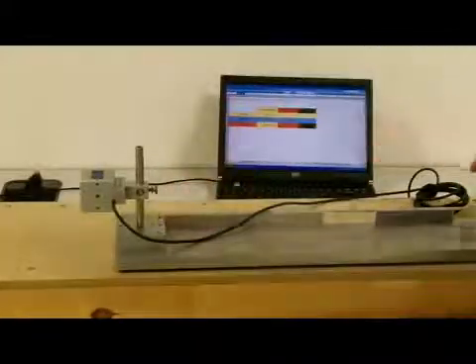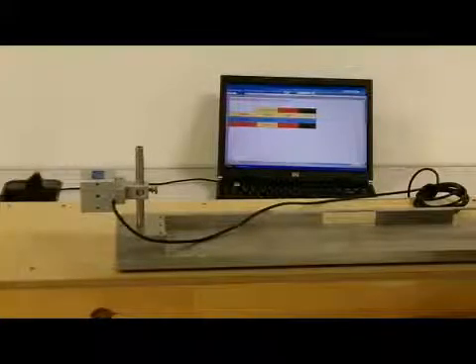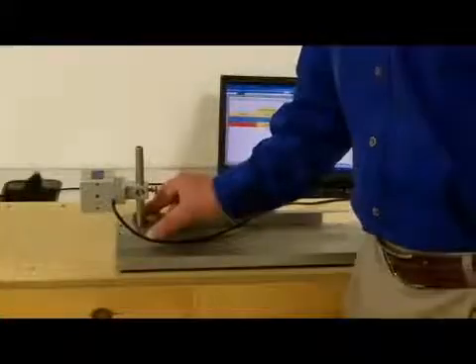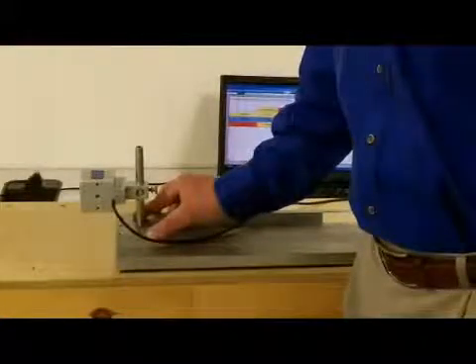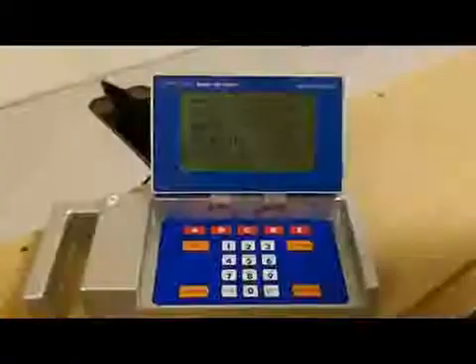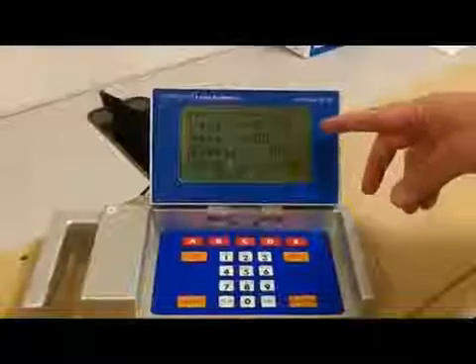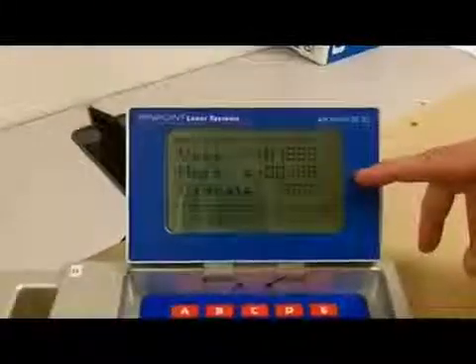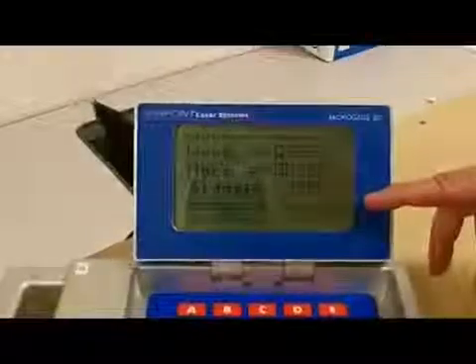To demonstrate the bucking in process today, I'm going to use two points on my rail to make my measurements, and these will be my calibration points, the points that I'll use for bucking in the laser. So to begin the process I've set my receiver up in my location number one and I will now take readings on my display unit. As you can see the readings are clearly displayed in real time on the display unit. I have a vertical reading of 0.1523 and a horizontal reading of 0.0120 with a strong signal strength.